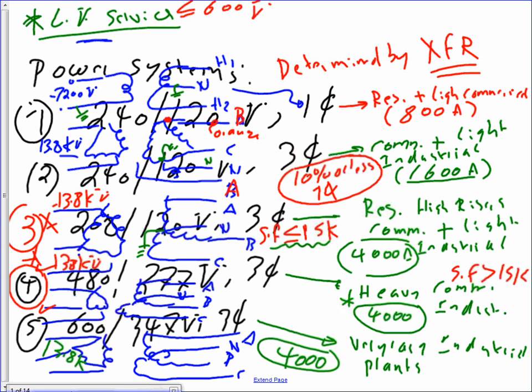Then we move into system number 4, guys. System number 4 is 13,800 volt on the primary. On the secondary, we have 480/277, 3-phase. This is heavy commercial and industrial. If your building is more than 15,000 square foot, can you just see that? That would be a good recommendation.